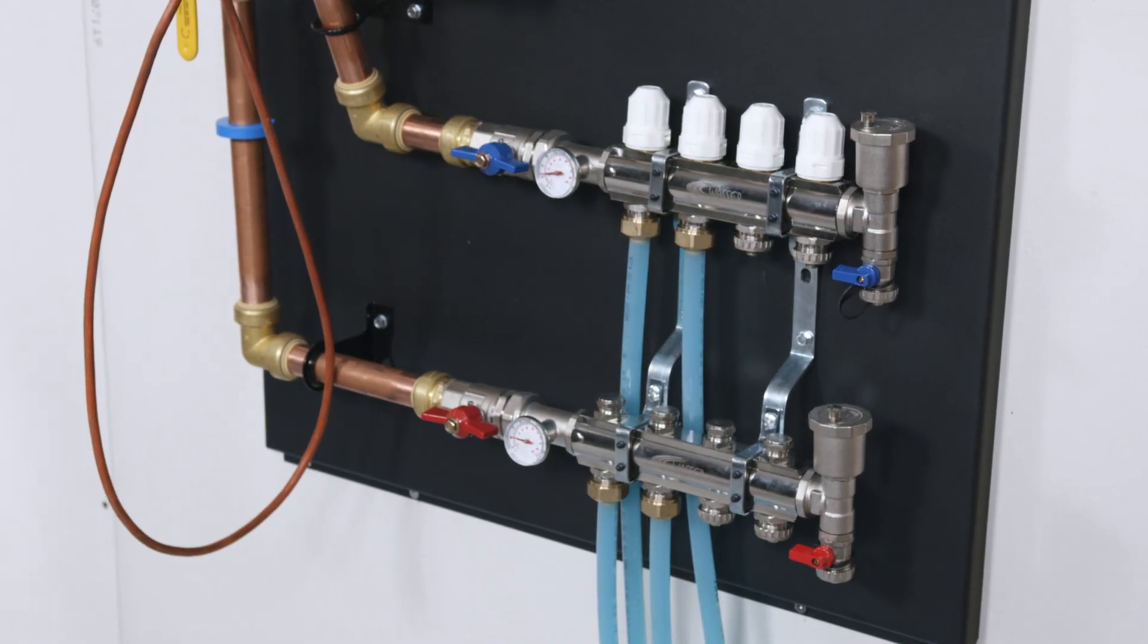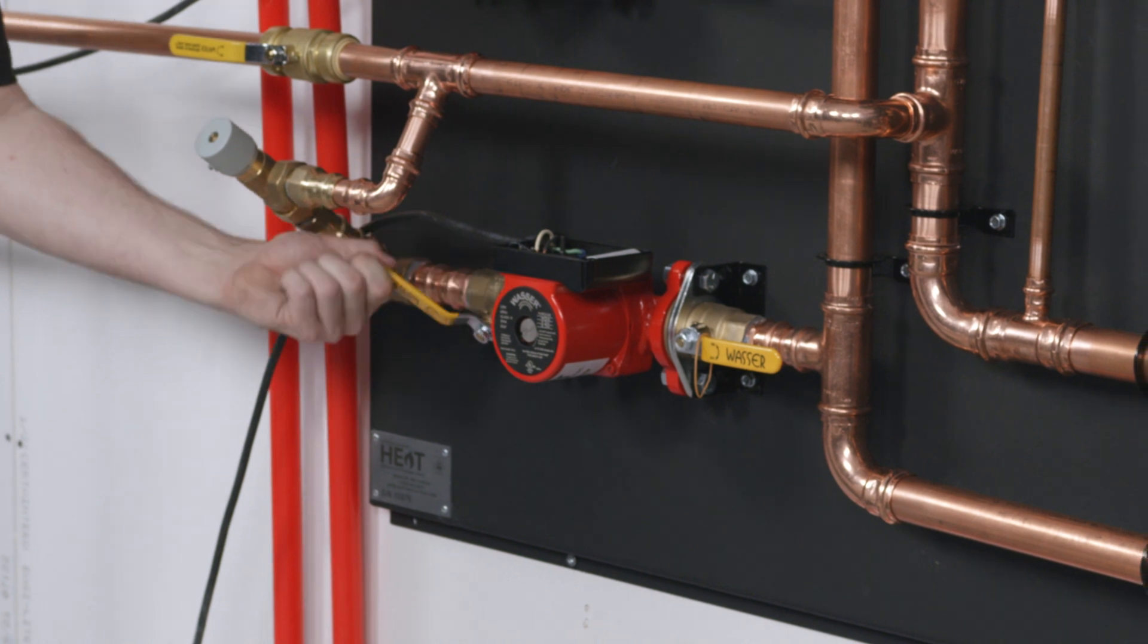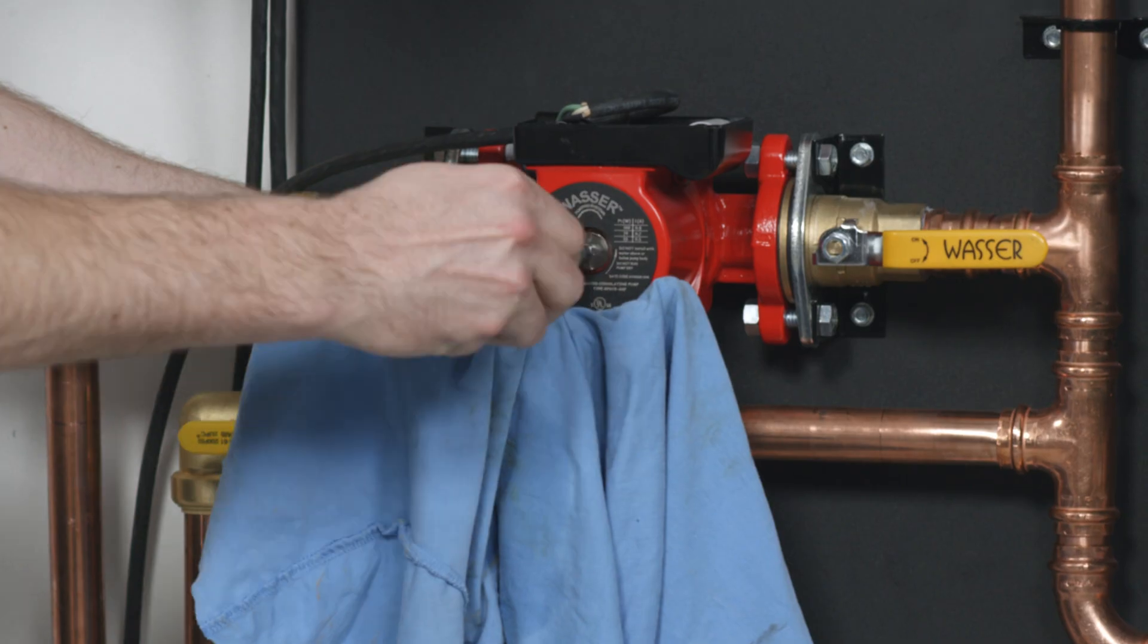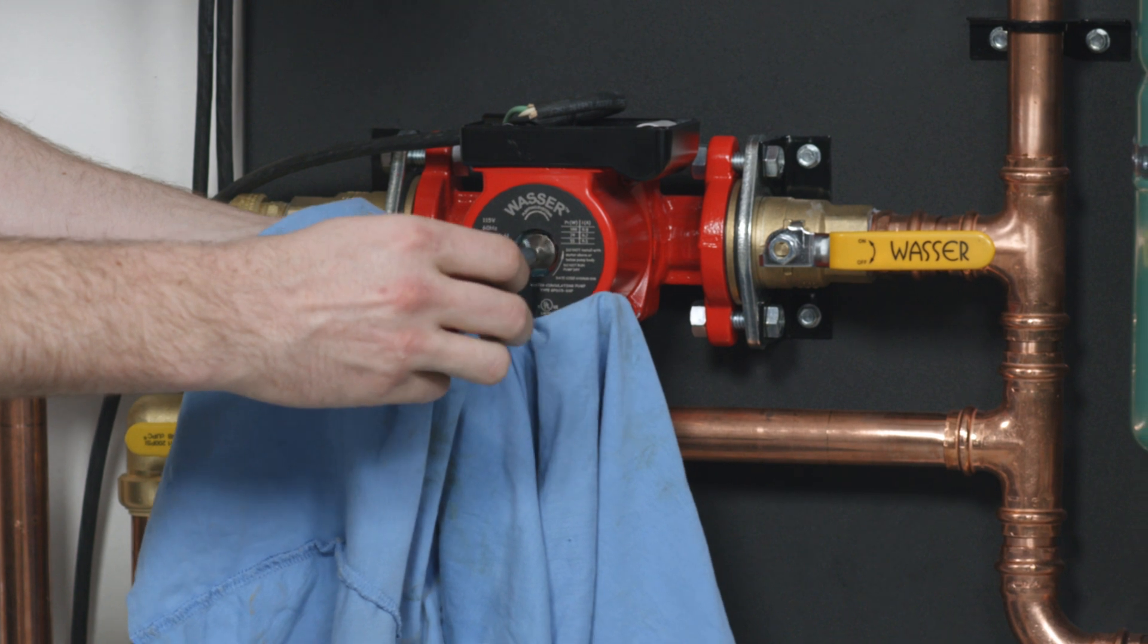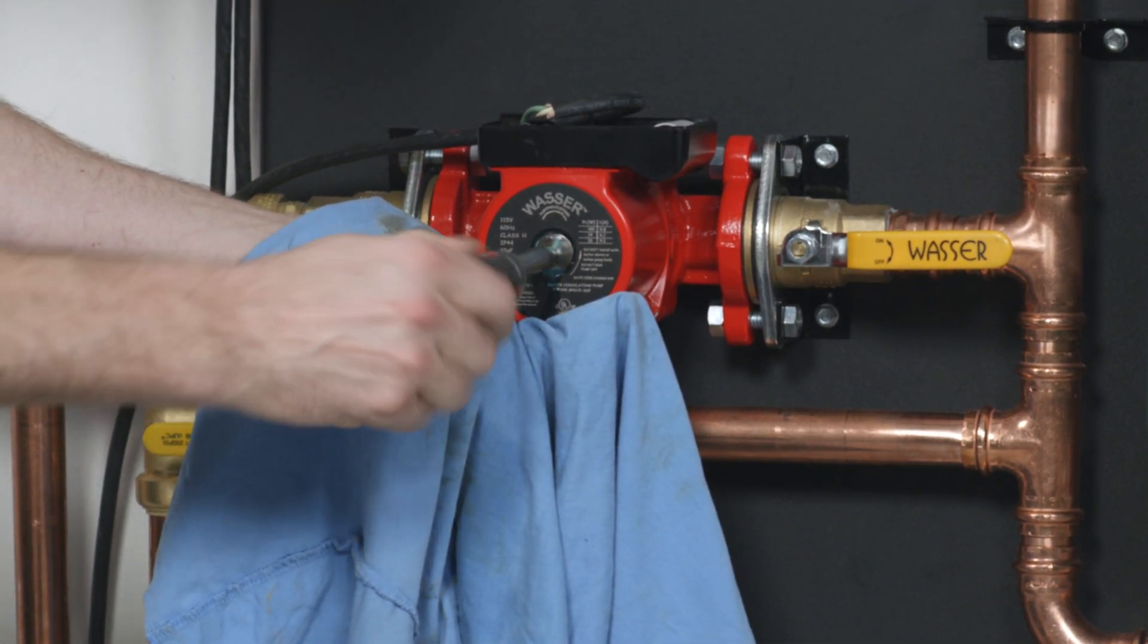If water isn't moving, you may have an air lock. Try quickly opening and closing a valve on the pump flange. You can also carefully loosen the bleed screw on the front of the pump to release any air stuck inside it.